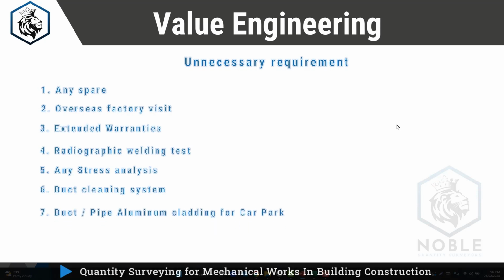The next is duct and pipe aluminum cladding for car parks. Some consultants may ask for aluminum cladding inside the car park also, for ducts and pipes running there, which may not be required. Aluminum cladding is only required for ducts and pipes running in exposed areas, directly exposed to sunlight, or in mechanical rooms. In the car park, you don't need any cladding for ducts and pipes, so this also can be removed if required in the specification.